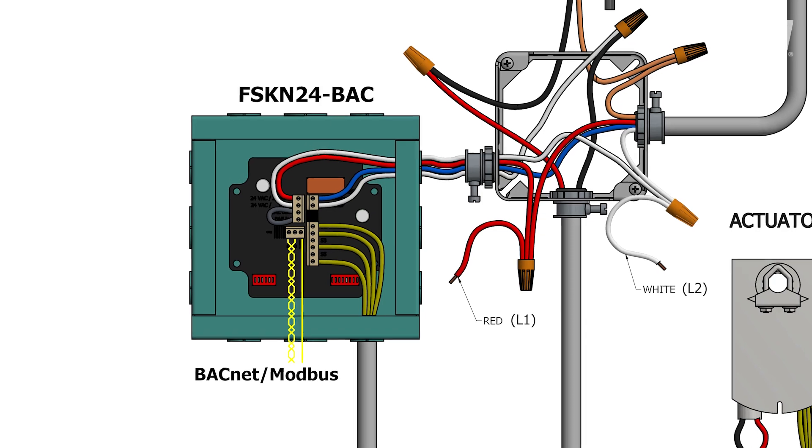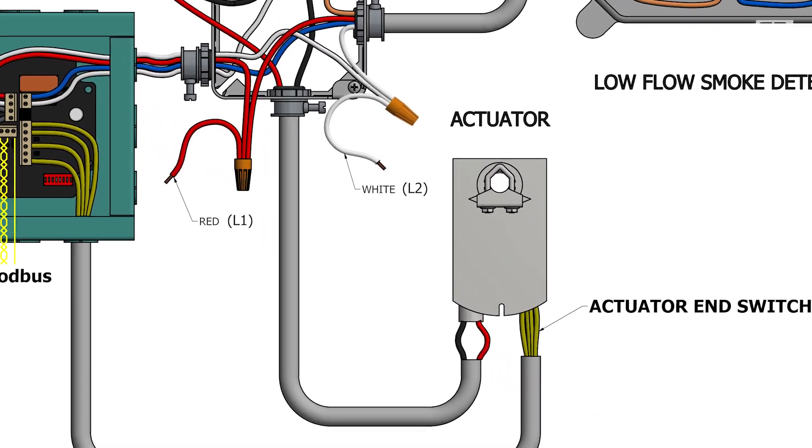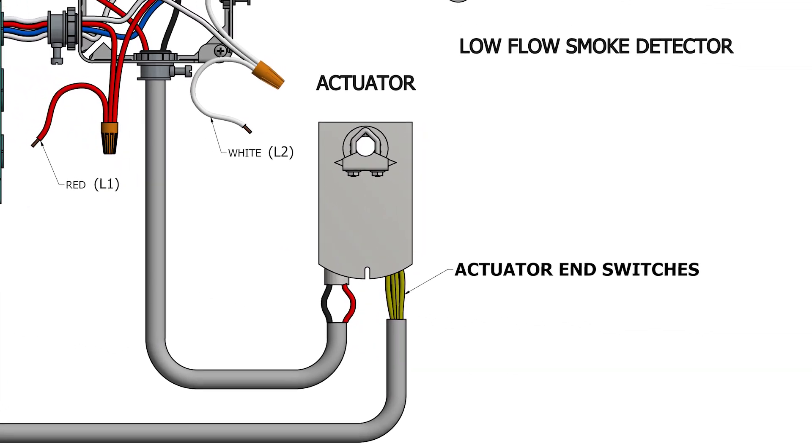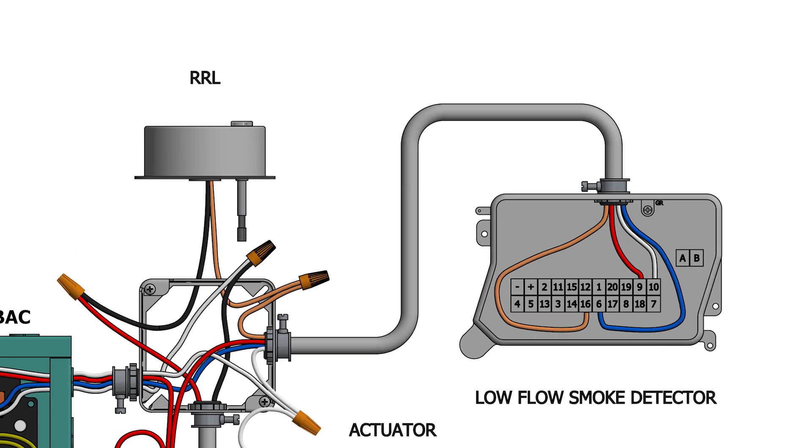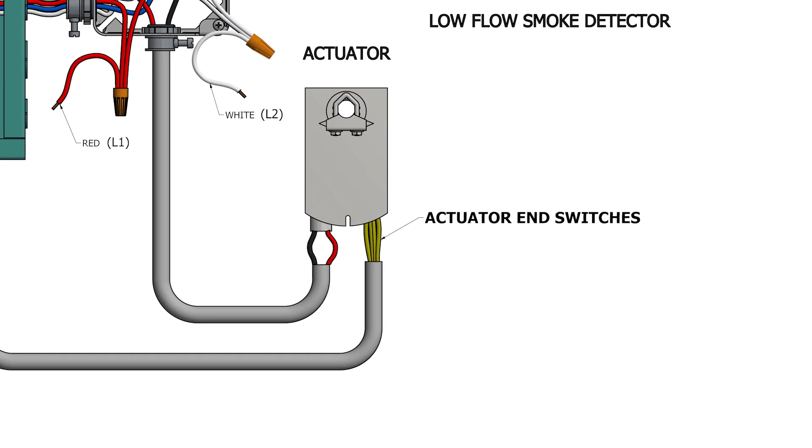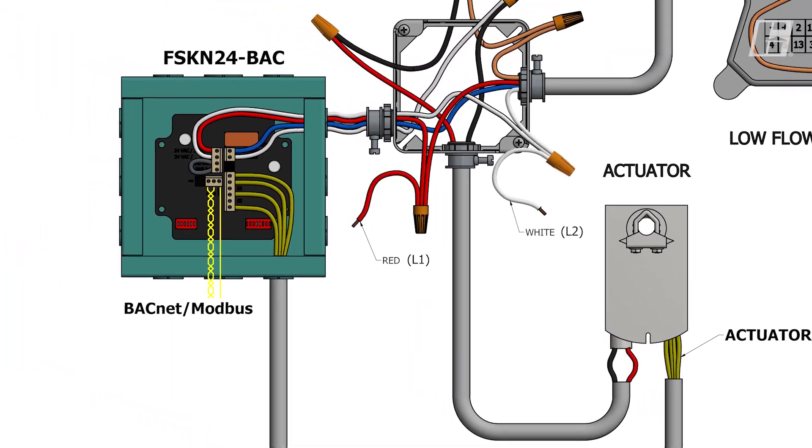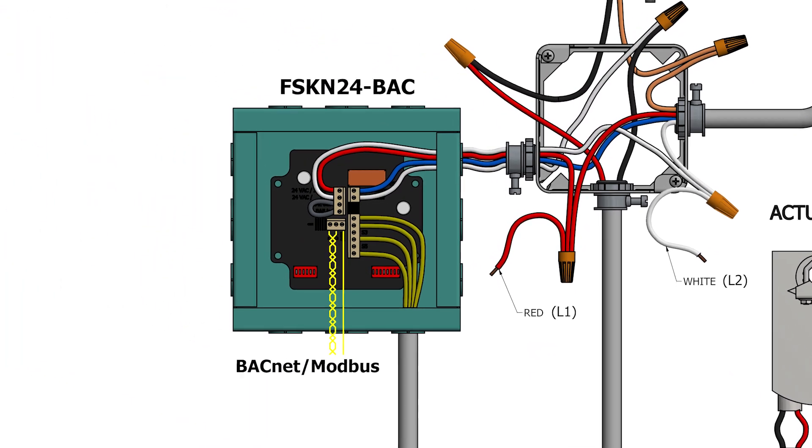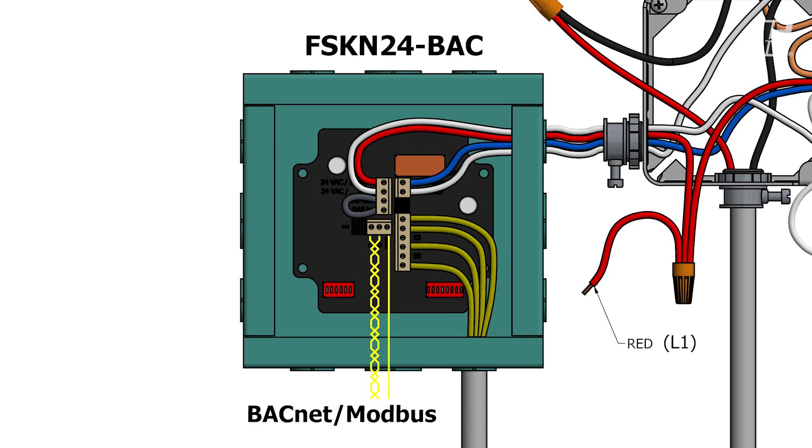Power is applied through the FSKN and wired in series with the damper actuator as well as the heat response device and smoke detector depending on the type of damper. Damper position indication switches are wired back to the FSKN for monitoring. BACnet or Modbus connections are also made to the FSKN for communication with the building automation system.